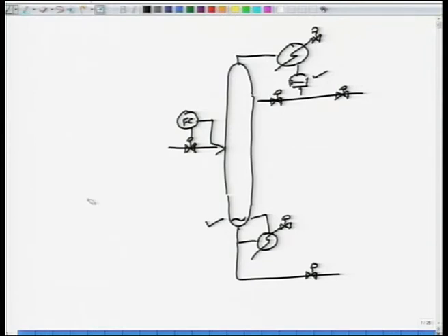And depending on how the level controllers are set, the level controller may be set this way. Pressure controller typically always is using cooling rate. That leaves the operator to set this and this, therefore, reflux is called L, reboiler duty is called Q, this is the LQ structure.